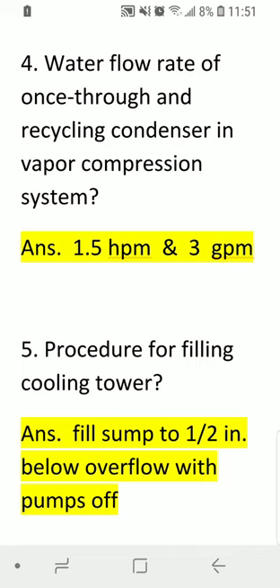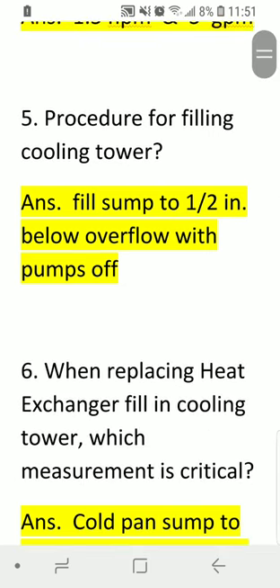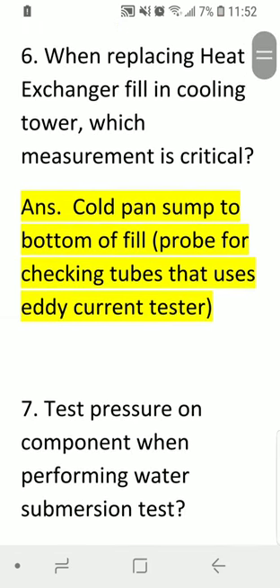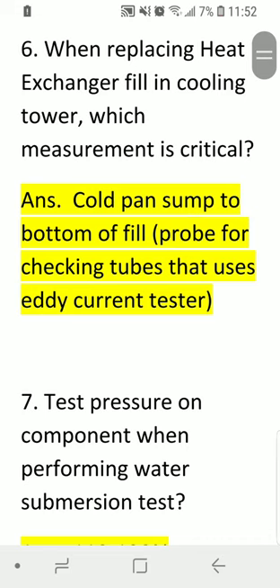Question five: what is the procedure for filling a cooling tower? Answer: fill the sump to one half inch below overflow with pumps off. Question six: when replacing a heat exchanger fill in a cooling tower, which measurement is critical? Answer: cold pan sump to bottom of fill probe.